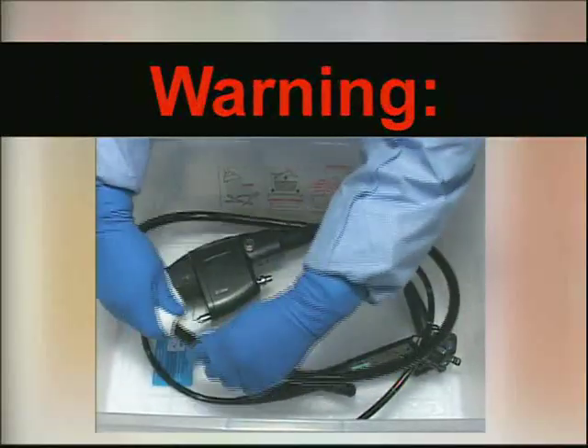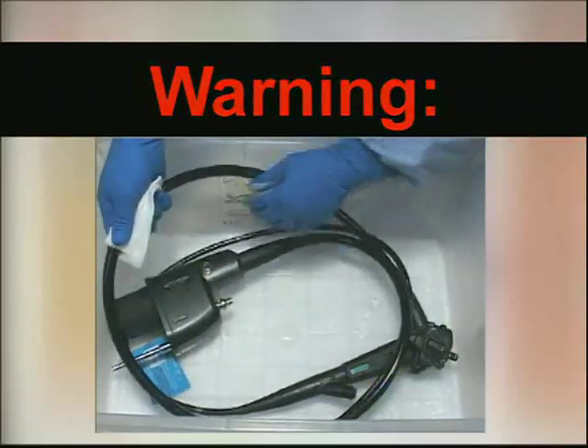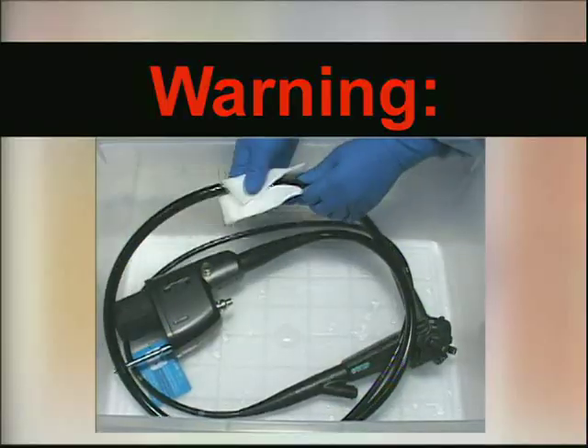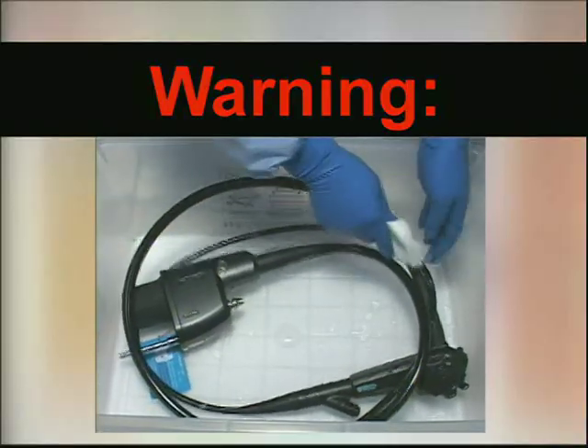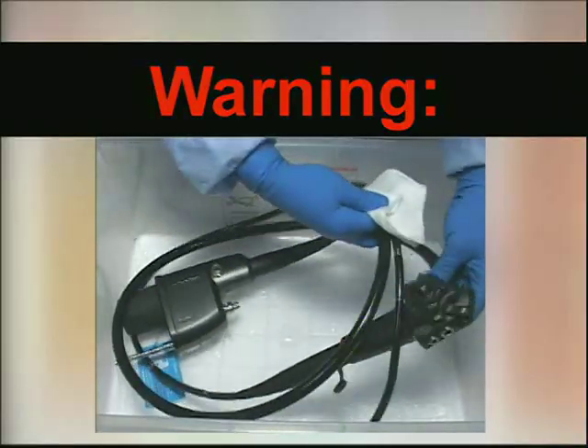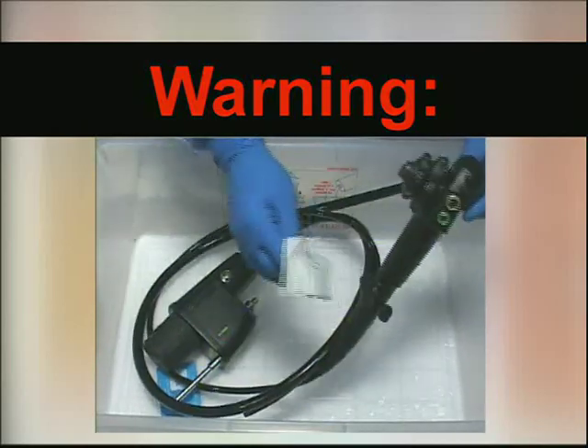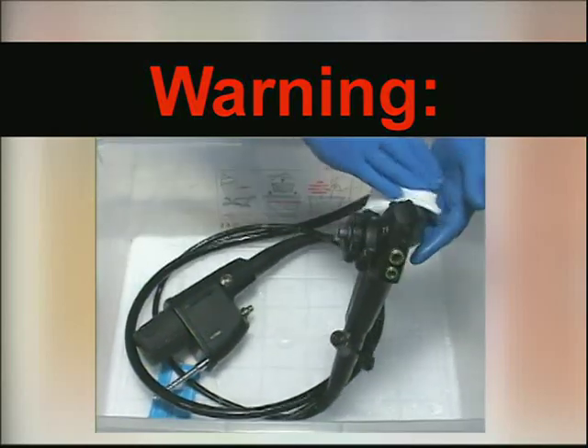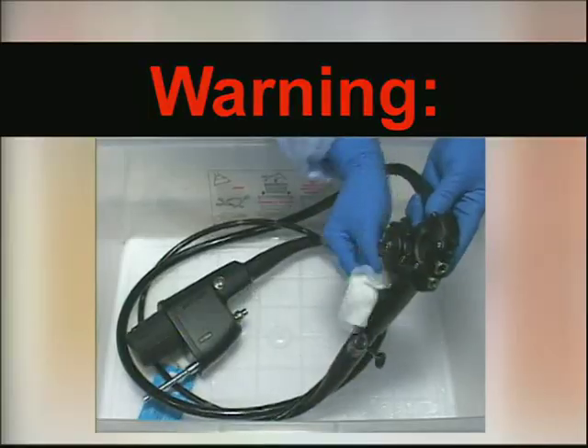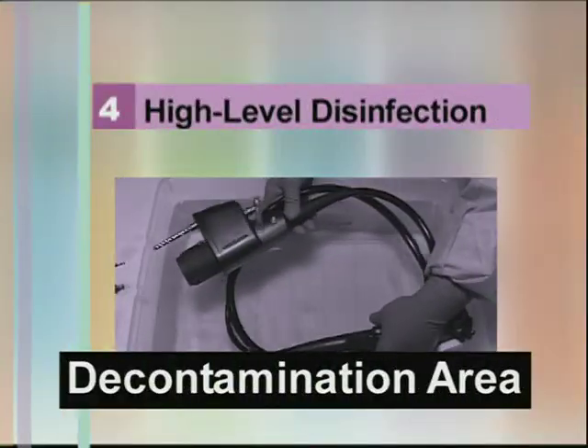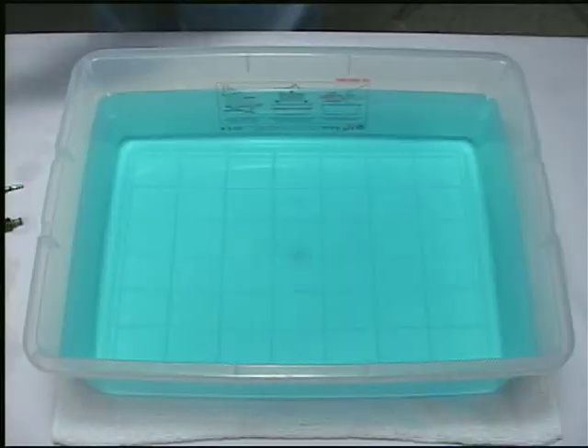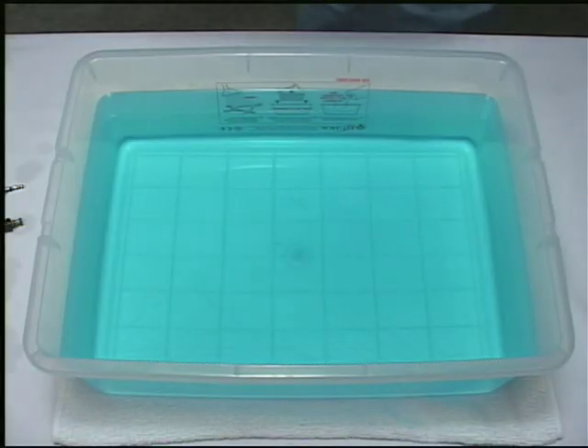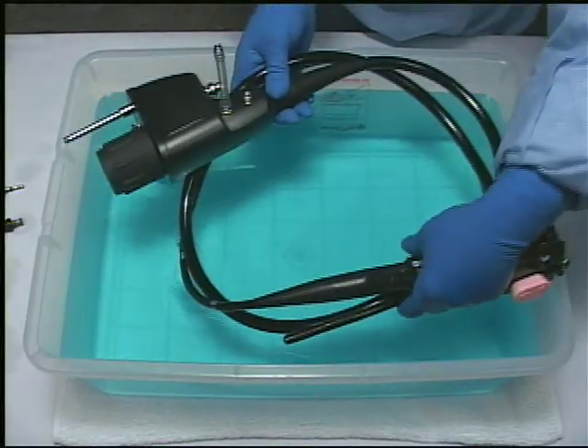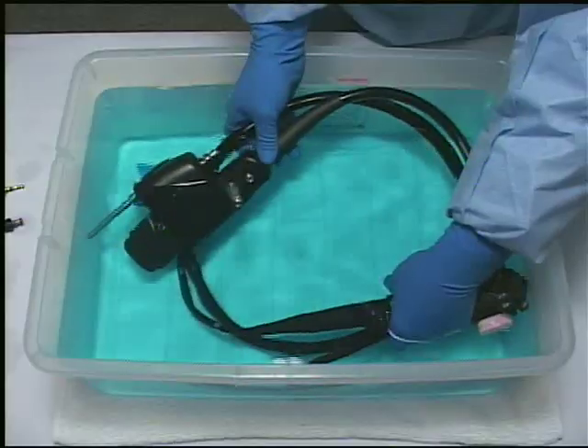Warning: prior to disinfection or sterilization, it is imperative that any solutions previously used in the cleaning process be thoroughly rinsed. Failure to do so could result in ineffective or incomplete disinfection or sterilization. High-level disinfection. Before any attempt is made to disinfect the endoscope, the entire cleaning procedure must have been completed.